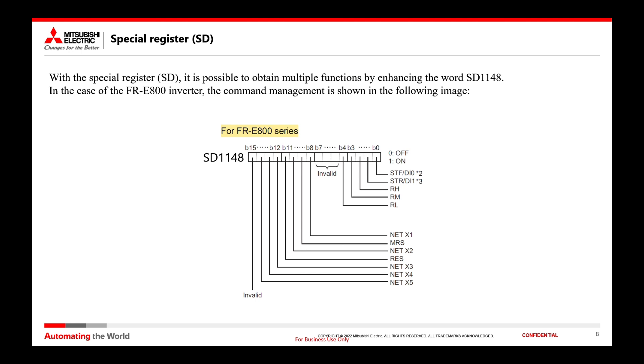The special registers represent the second method available to program the PLC. Unlike the special relays, here the SD register is always used, which is represented by the word SD1148, and through the combination of bits we can obtain multiple functions. So in the case of the E800 inverter, for example, if I wanted the forward command at the RM speed, I would have to write in hexadecimal H9.